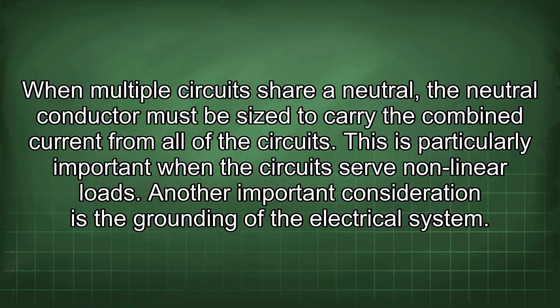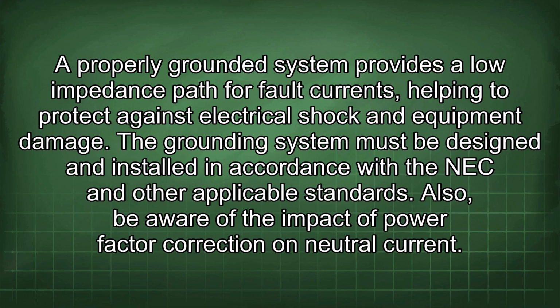Another important consideration is the grounding of the electrical system. A properly grounded system provides a low impedance path for fault currents, helping to protect against electrical shock and equipment damage. The grounding system must be designed and installed in accordance with the NEC and other applicable standards.